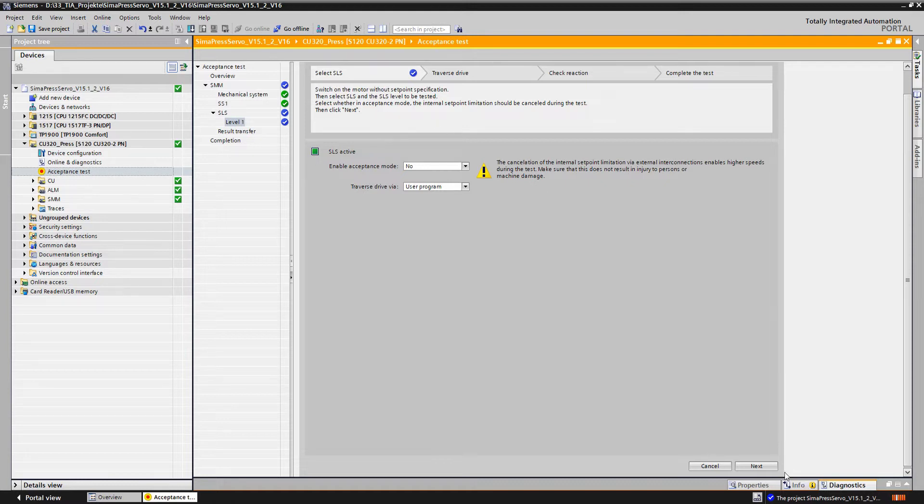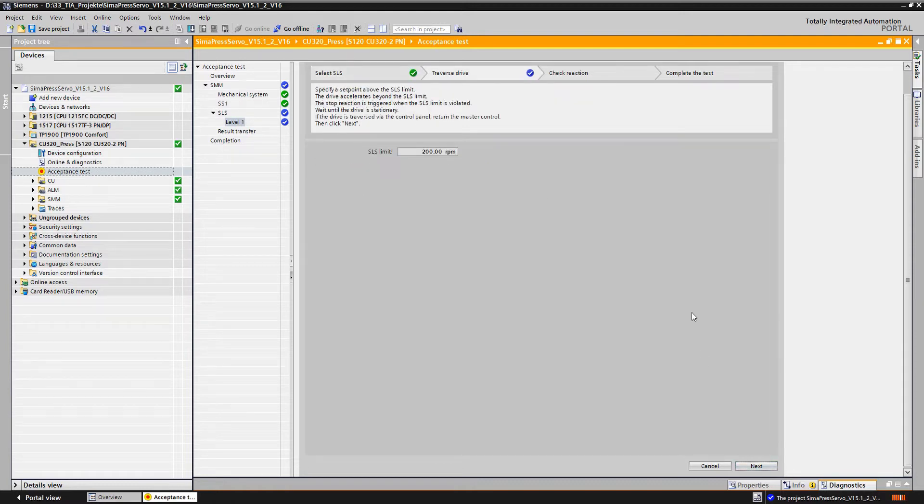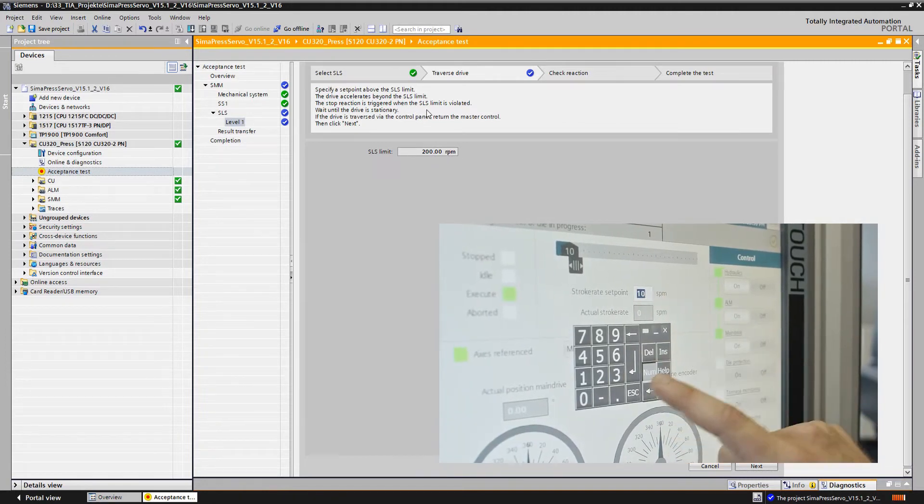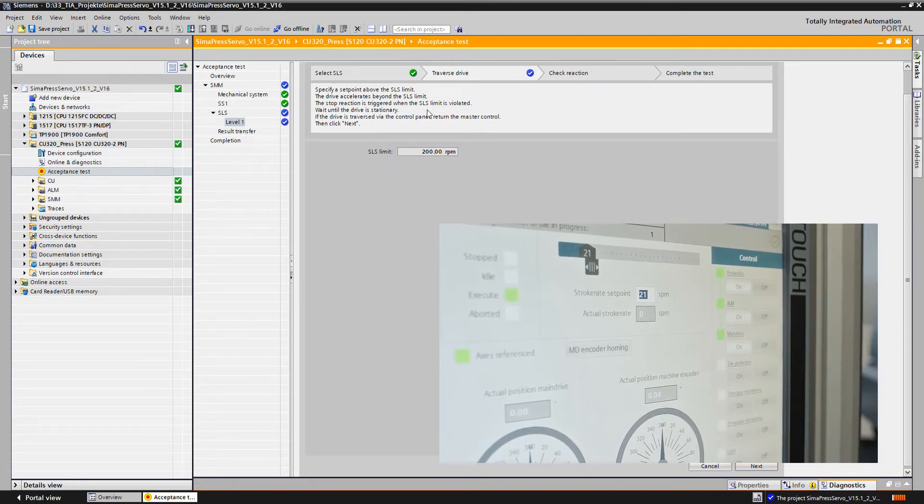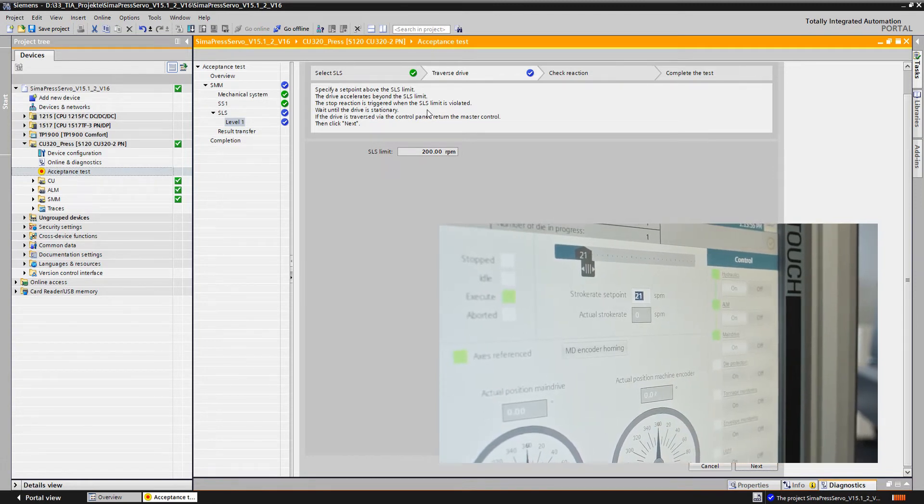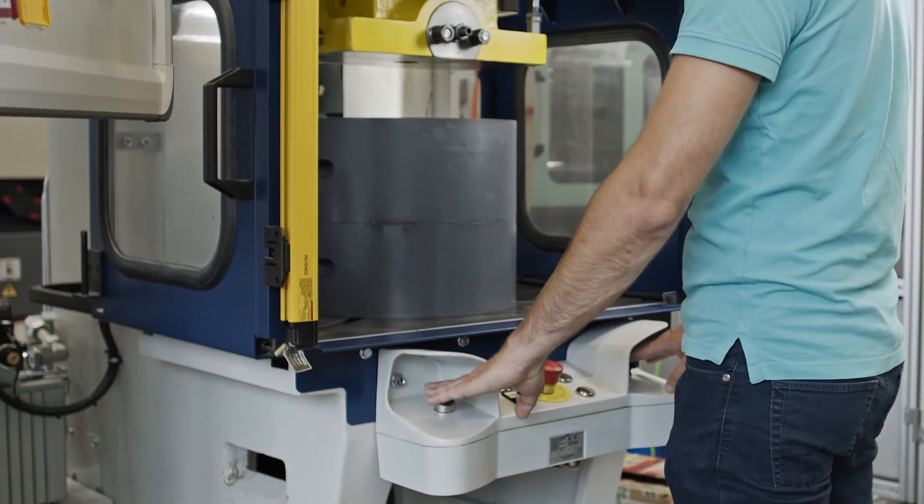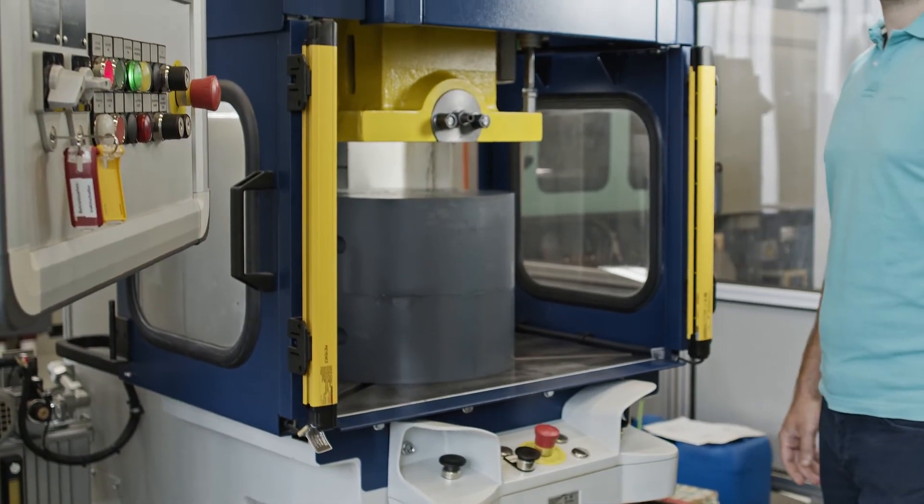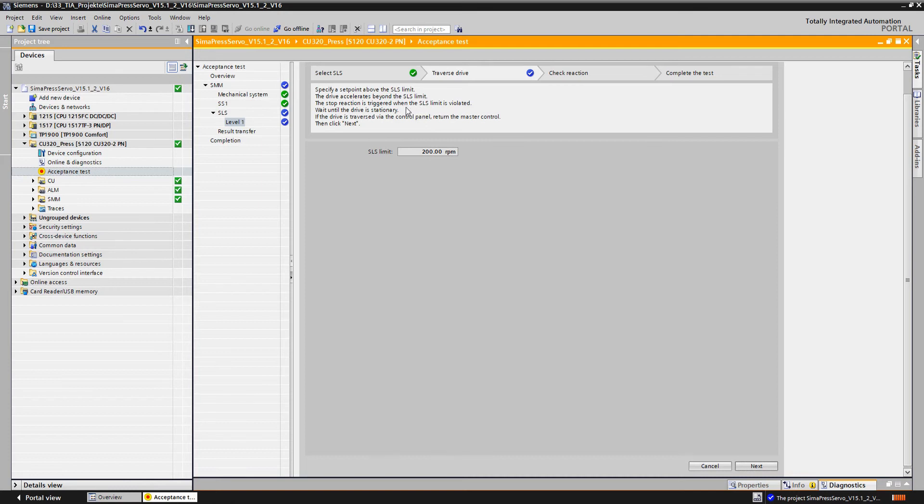In our example, the SLS limit is to be exceeded again via the control panel, in other words, the user program. We specify a set point above the SLS limit, for example 21 strokes per minute. The movement of the machine is now started again by means of two-handed operation. If the SLS limit is exceeded, we wait for the stop response and continue switching only when the drive actually stops.